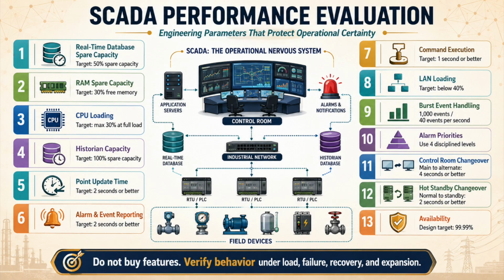Do not ignore alarm bursts, because alarm storms expose weaknesses in system design, alarm philosophy, operator interface, server capacity, historian capacity, and network architecture. Do not make network loading an afterthought, because SCADA systems are only as reliable as the communication architecture carrying their truth. Do not accept demonstrations as proof, because demonstrations show capability, while performance testing proves suitability. Do not treat control room changeover as paperwork, because main to backup and backup to main behavior must be tested, timed, documented, and understood by operators. Do not allow procurement pressure to compress engineering judgment, because the lowest cost SCADA offer can become the most expensive operational weakness when performance parameters are not enforced.